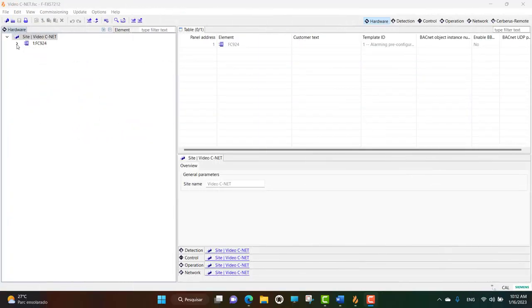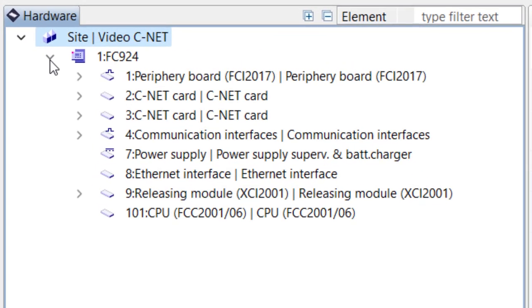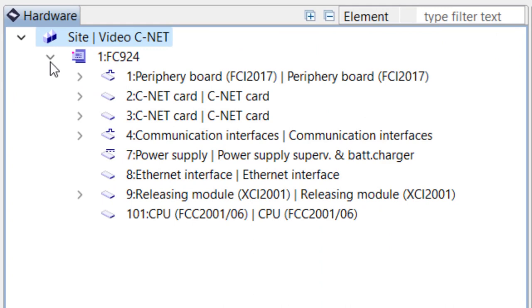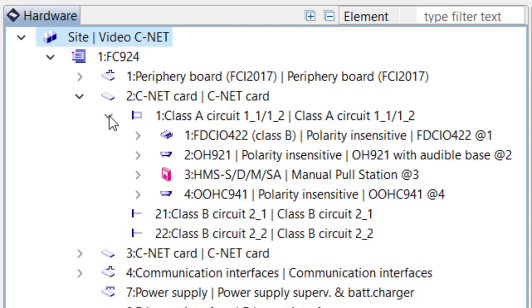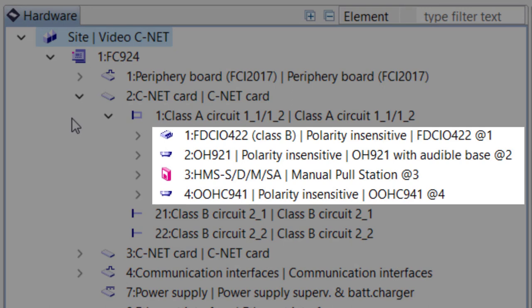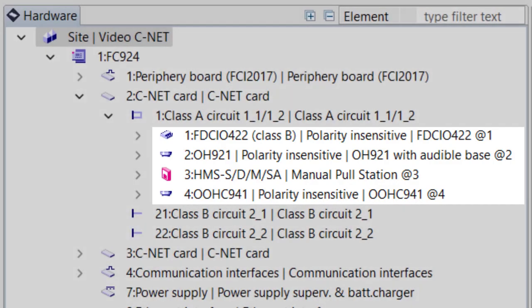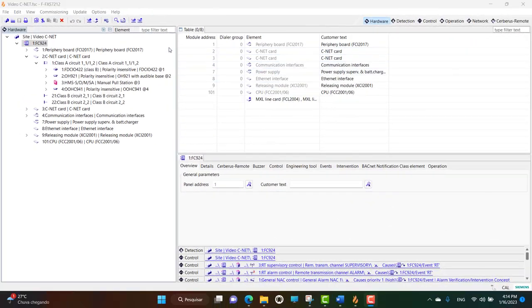First, let me show you my system's configuration. It is a simple configuration with four devices addressed from 1 to 4 and some other non-addressable devices such as audible bases, system relays, etc. One recommendation here is to include the device's address in the customer label text field in the configuration. This helps a lot when performing system maintenance later on. I have also configured my system for self-restoration of trouble and supervision conditions.